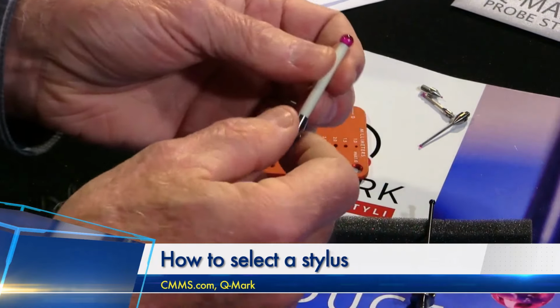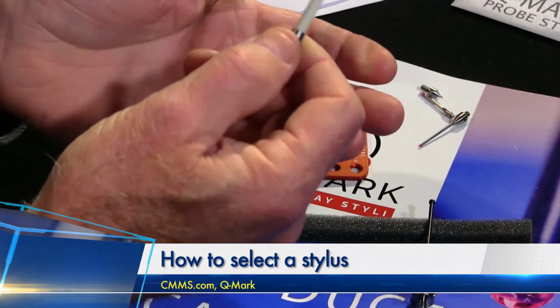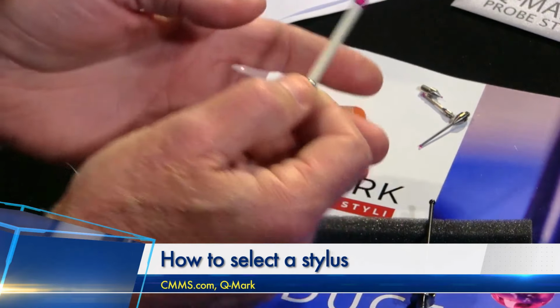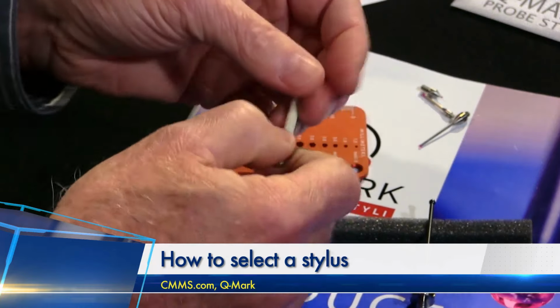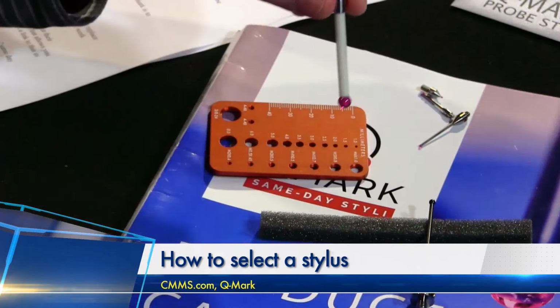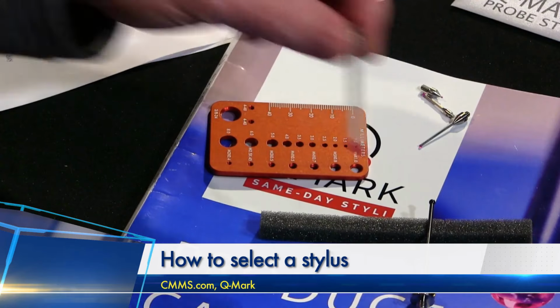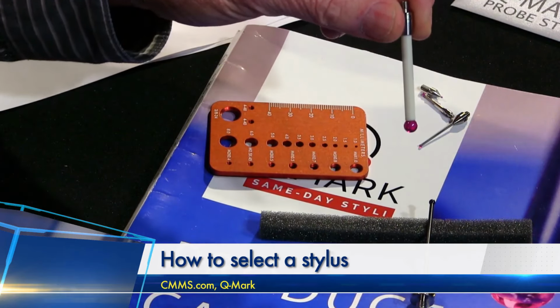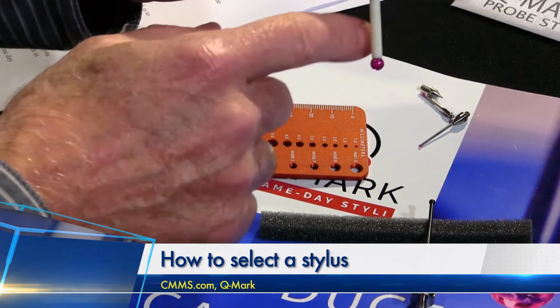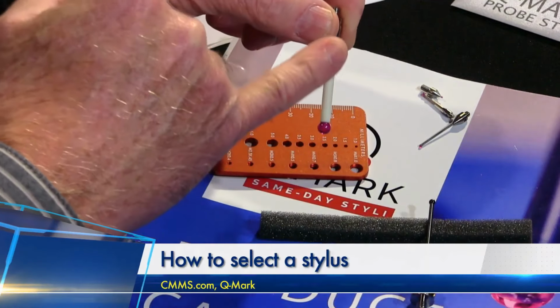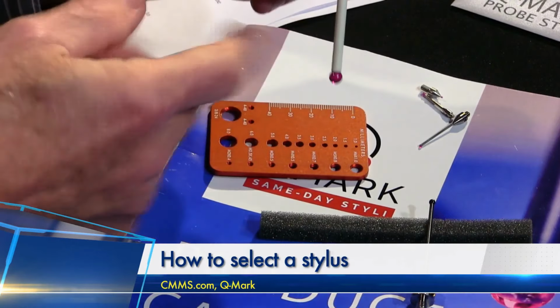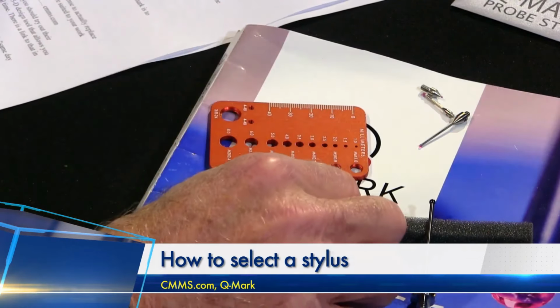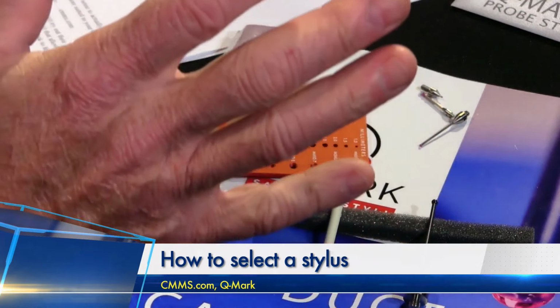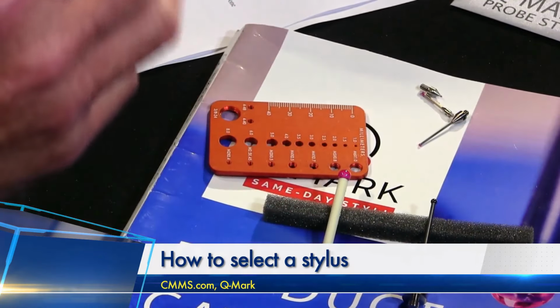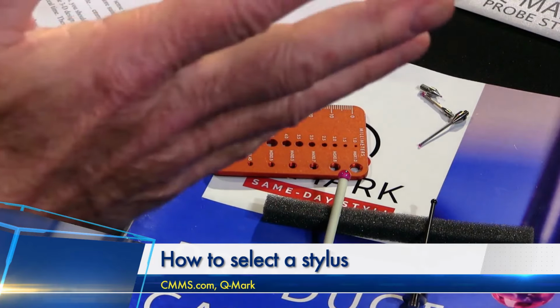And a lot of machinists, a lot of machine tool people go with ceramic stems like this one. And the reason is because it's brittle. So if you can imagine on a machine tool, if you're using this probe and you crash it into a part or a fixture, you would rather break an inexpensive stylus rather than break an expensive probe head. So you can think of this as a fuse that protects the probe head. So a lot of machine tool people will go with a ceramic stem. So think about those things for your application. You don't need to just blindly do a one-to-one replacement.